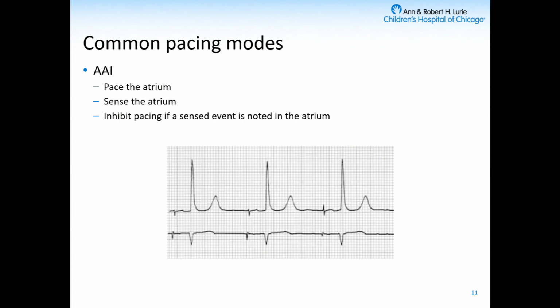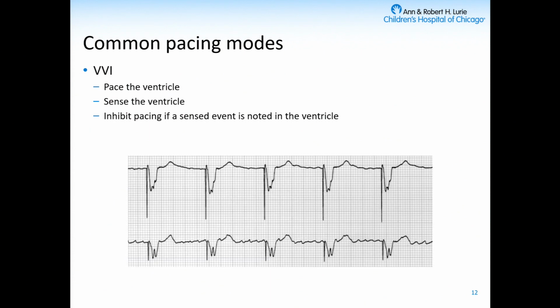So just a couple of quick reviews. This is what typical AAI looks like. Pacing the atrium, sensing the atrium, although you don't see any sensing here, these 3 beats are all paced. And then if there were a sensed P wave, then the device should not pace if it's working correctly.